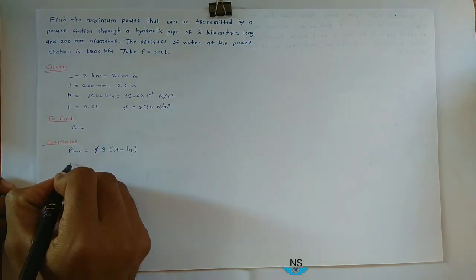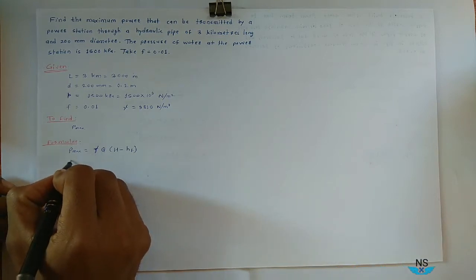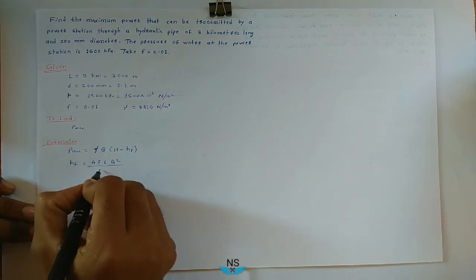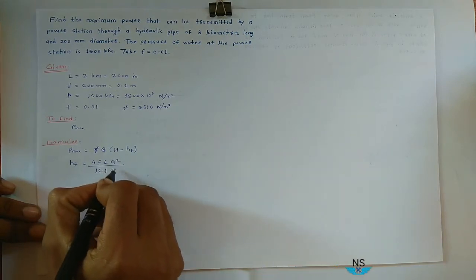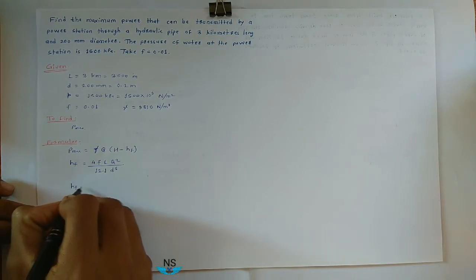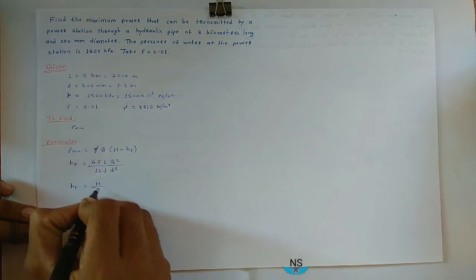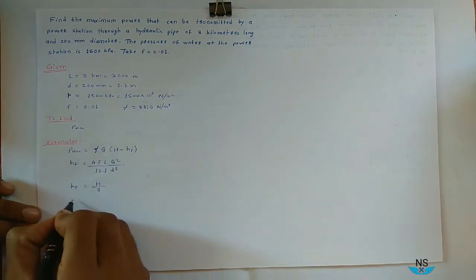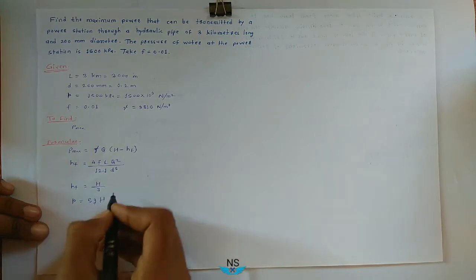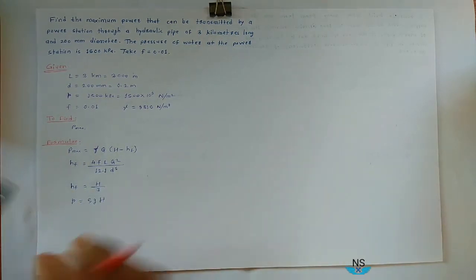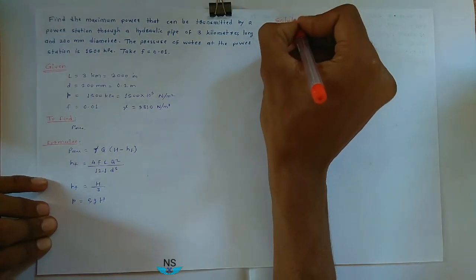We have to find Q from HF. HF is equal to 4 F L Q square divided by 12.1 into D raised to 5. For maximum power condition, HF is equal to H divided by 3. And H we find from pressure formula, P is equal to rho G H. So these formulas are required for solution.